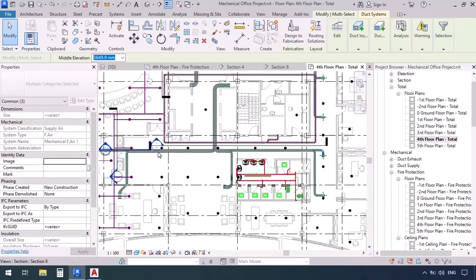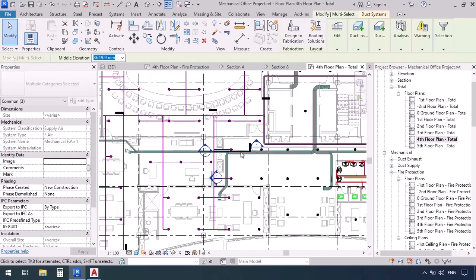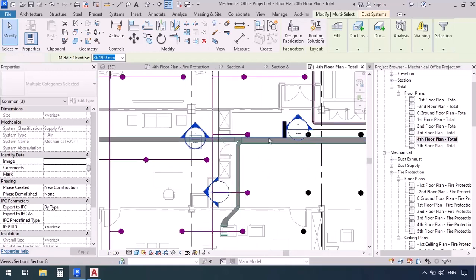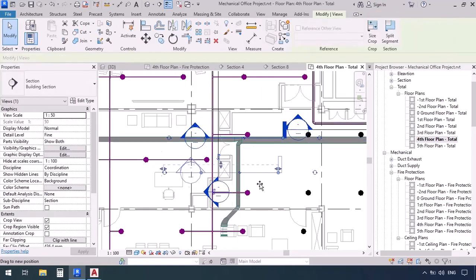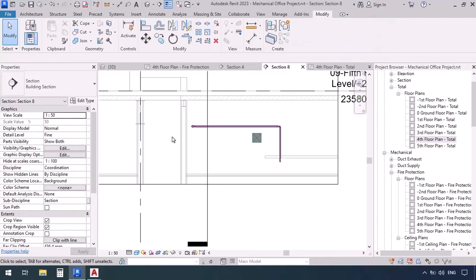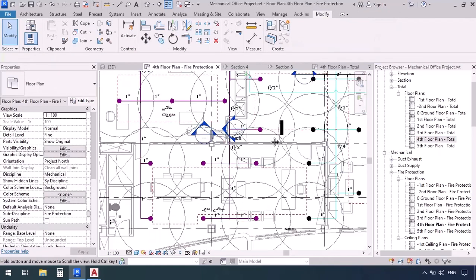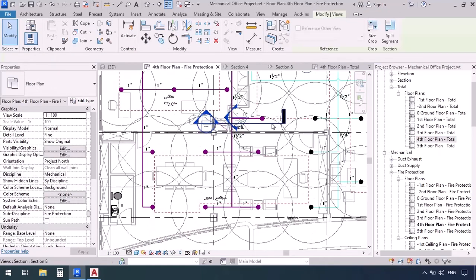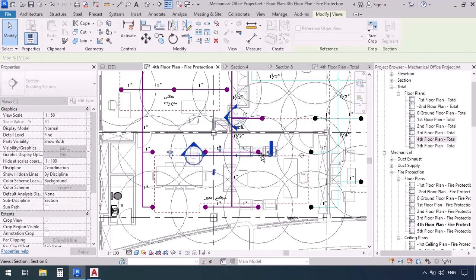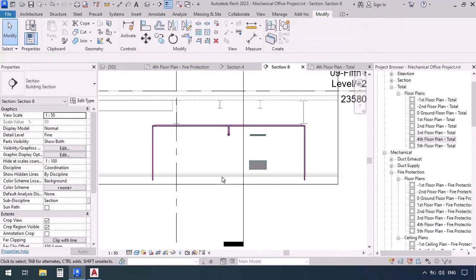So for the crossing we checked the total plan instead of just that part. Once again I'm going to take the section and put it right here and double check. The pipe is going right above the duct so it's okay. Then for this other part where we increased the elevation we were able to clear the crossing here as well.